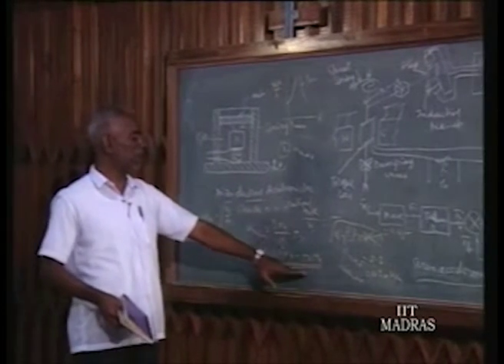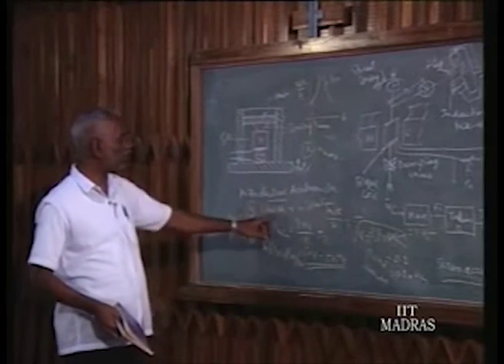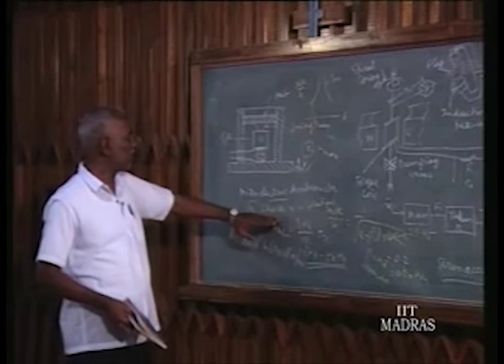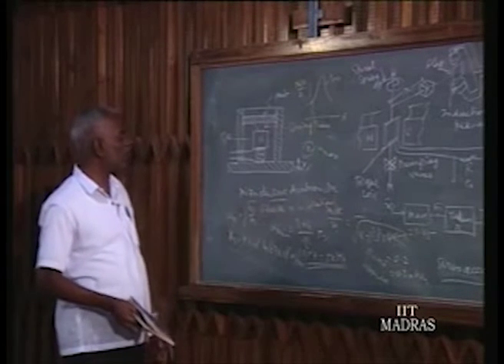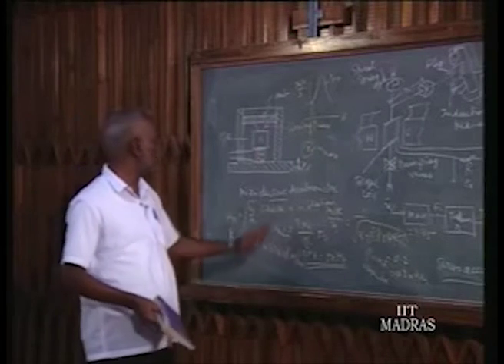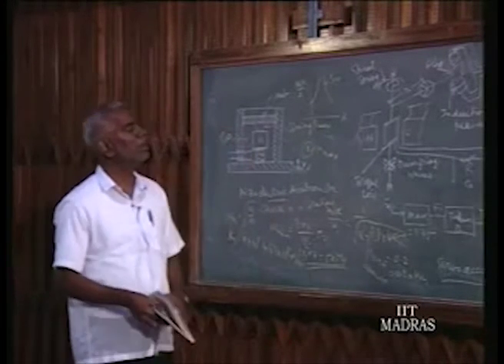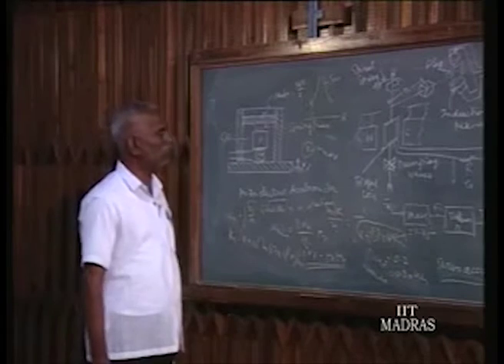So 240 hertz will be maximum. Hence they cannot be used for measurement of shock where acceleration is varying at very high frequencies. You cannot use it. So in such instances we have to go only for this piezoelectric accelerometer.